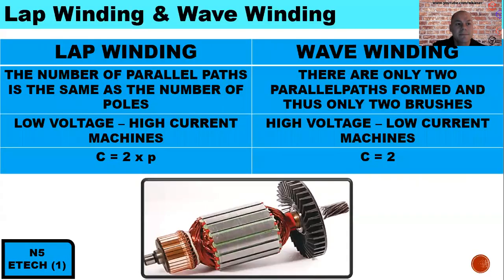Our next concept is lap winding and wave winding. The armature conductors in the armature assembly could either be wave wound or lap wound. For a lap wound armature assembly, the number of parallel paths is the same as the number of poles. It is used for low voltage and high current applications. The small letter C represents the number of parallel paths; therefore for lap winding it will be 2 times small letter P, which is the pole pairs.